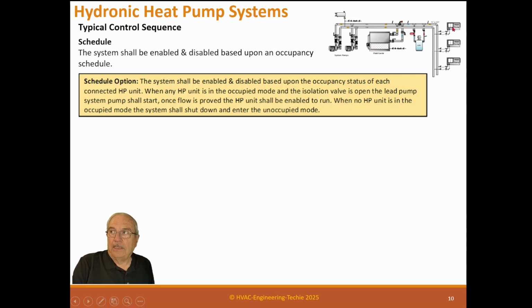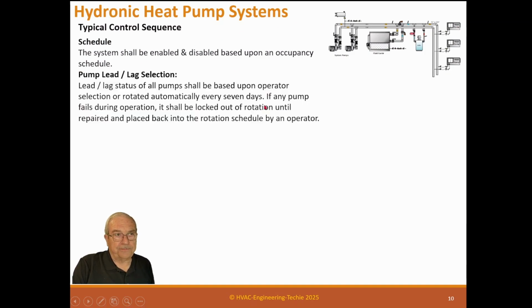So if this is in the unoccupied mode and they're all off, and one comes on and this valve opens, then it sends a signal to the central plant to start. The central plant starts and proves flow, and then it unlocks this unit and allows the compressor to run. Can't run it unless this has flow in.